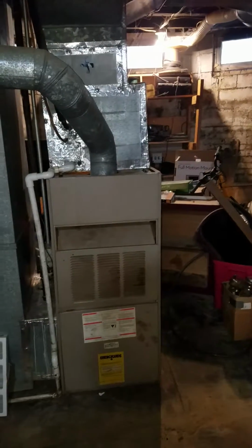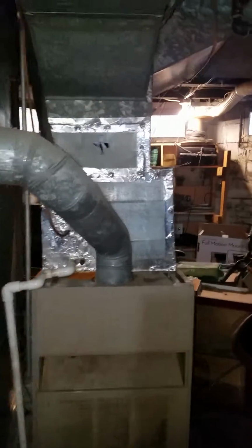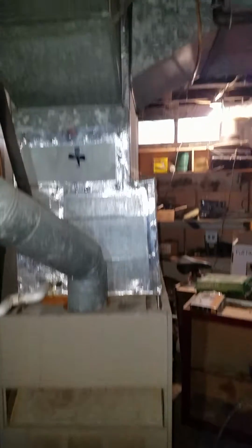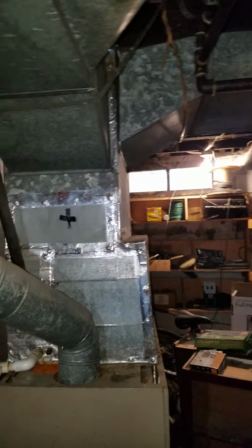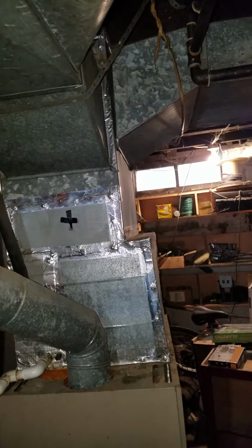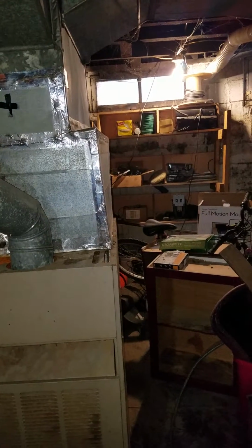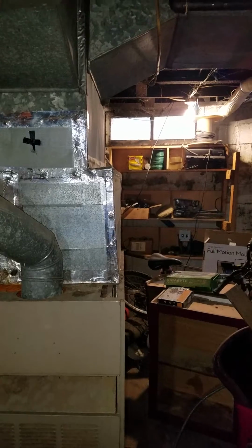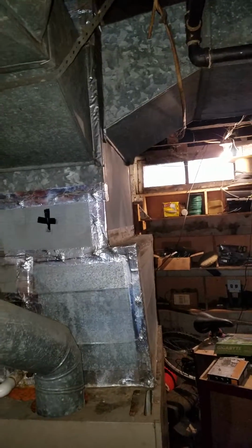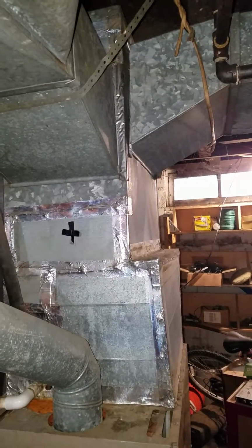So a couple of things I want to talk to you about. Your coil is very restrictive to the current furnace that's in here, but then we slim down on our ductwork above that coil. So you're down below, you're 18.5 by 22, and it's okay as far as coming close to matching the furnace, but then you get up here and you're restrictive even up above the furnace.